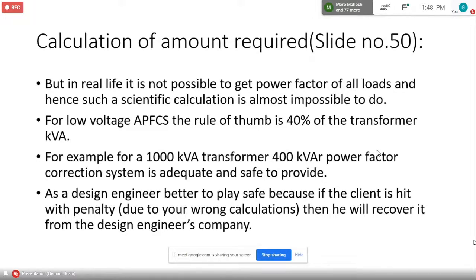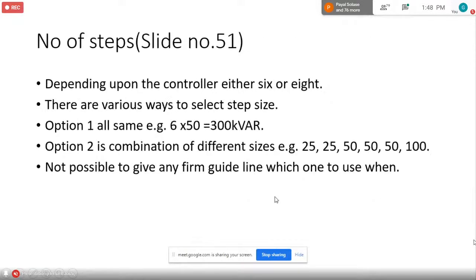So you can do this calculation in 1 minute and you are absolutely safe. As a design engineer, it is better to be safe, because if the client is hit with a penalty due to wrong calculation, then he will recover it from the design engineer's company. Actually, 30% is also good enough in most cases, but I will never take a chance because of this. If by chance it is not adequate, then the client will say, I have been penalized for bad power factor, Mr. Design Engineer, you pay me. Don't take risk.